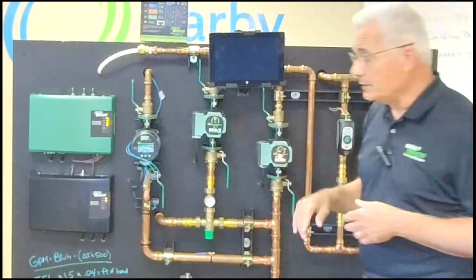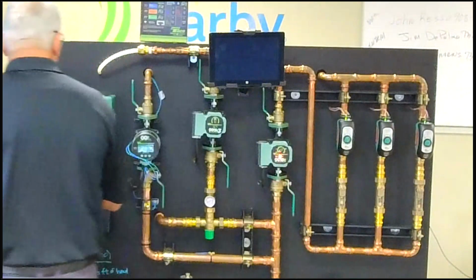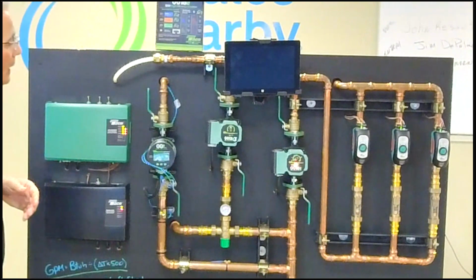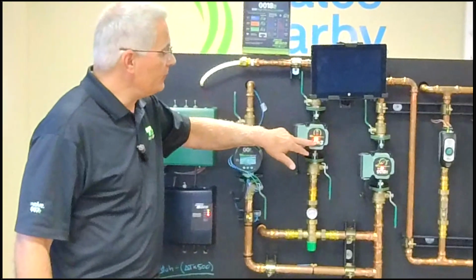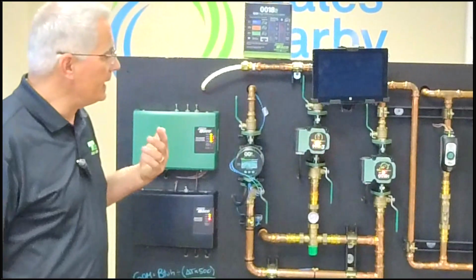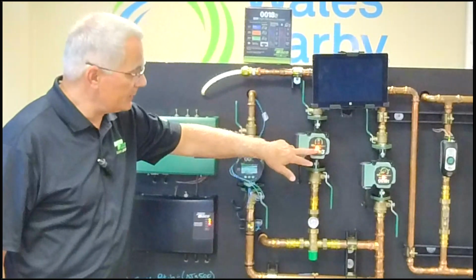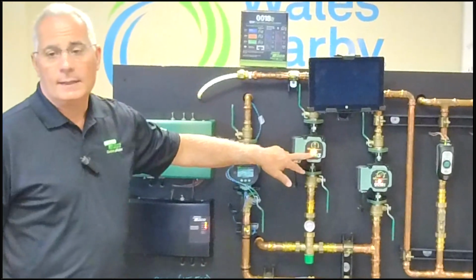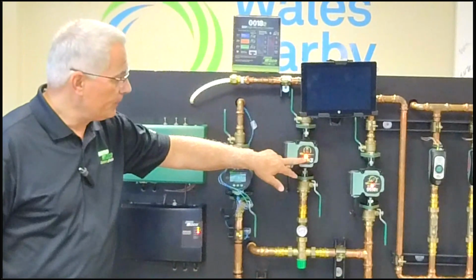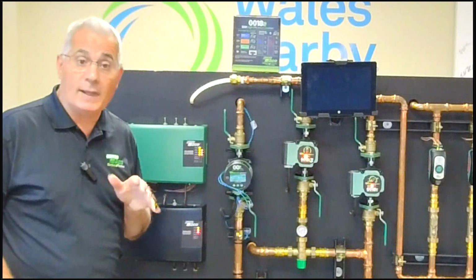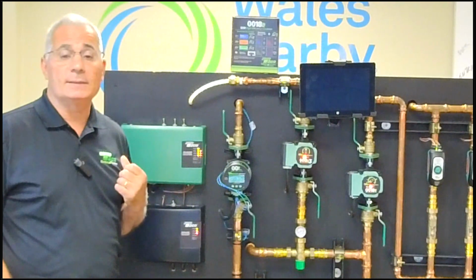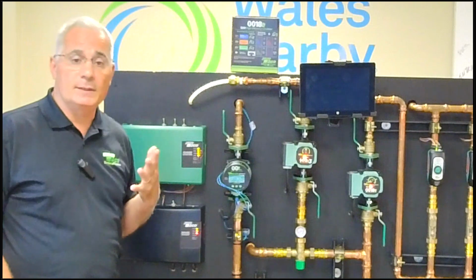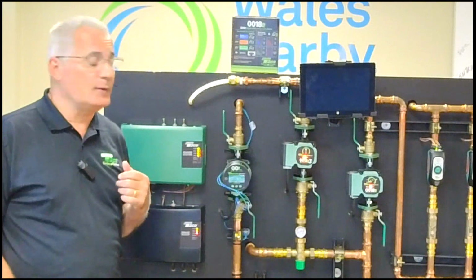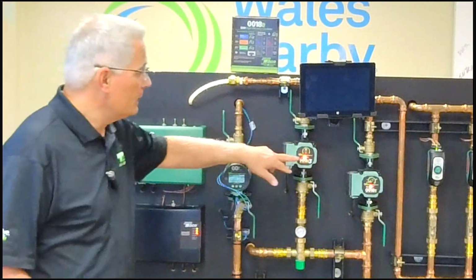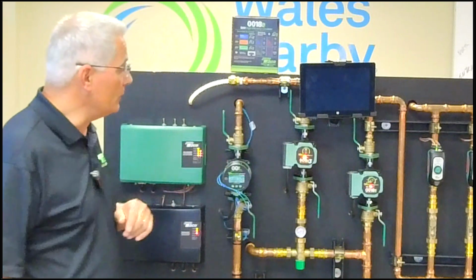So I'm going to turn this circulator on by flipping this switch. Now you're going to see the light flash on any of our ECMs, and since we're in a constant pressure mode, you're going to see the orange light. That first flash of white you saw, if it came through on the camera, was we initially turned on and it's checking for air. There's no air in the system, so we're in normal operating mode.